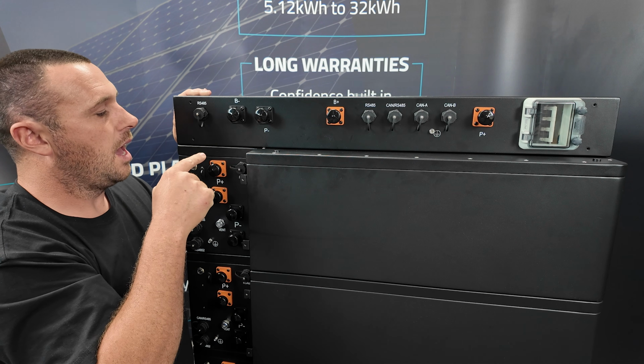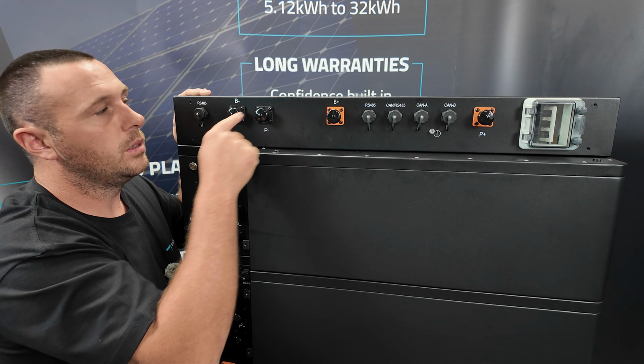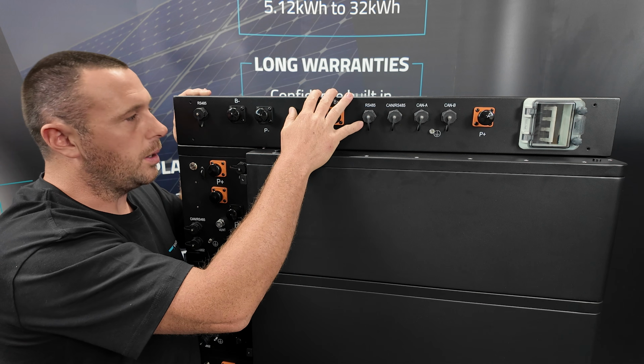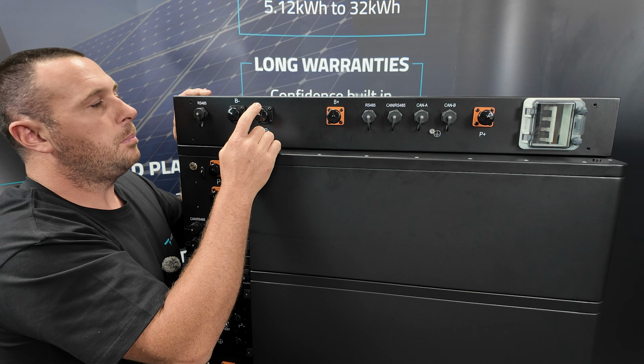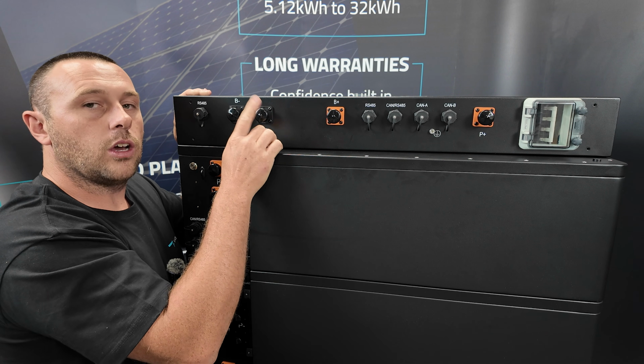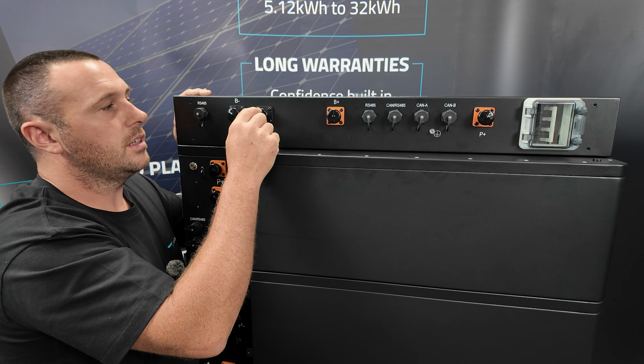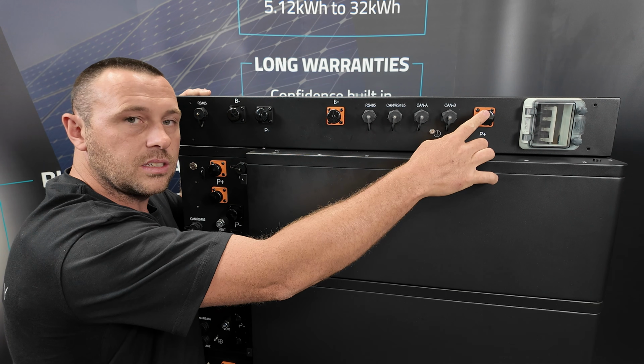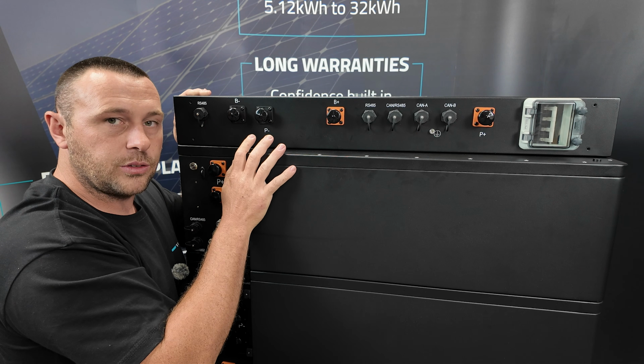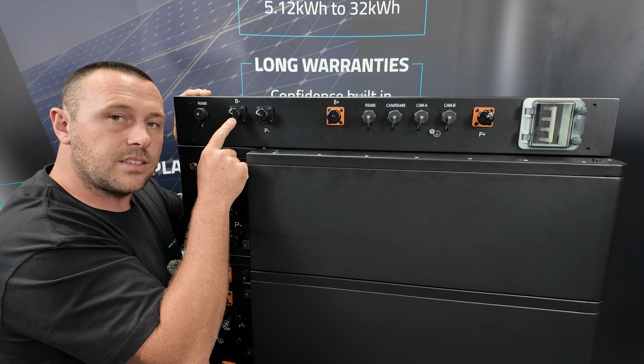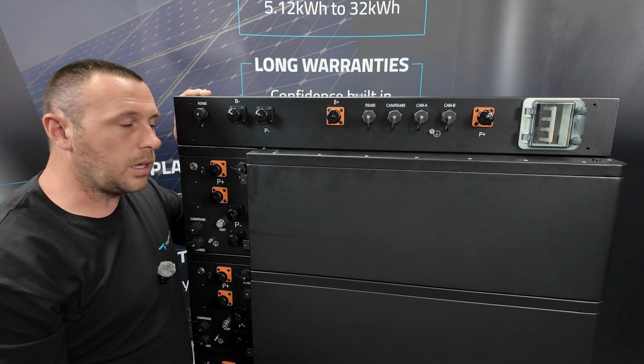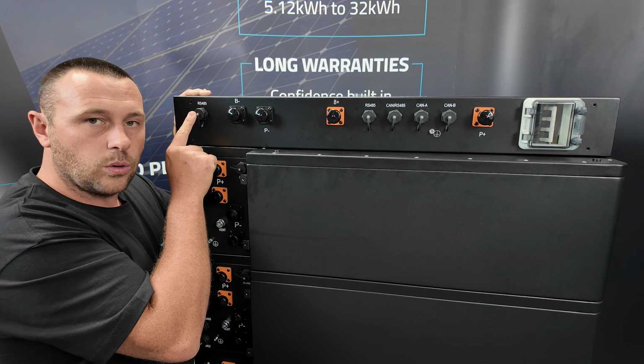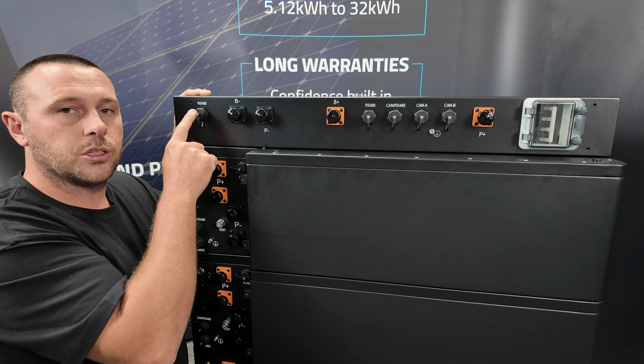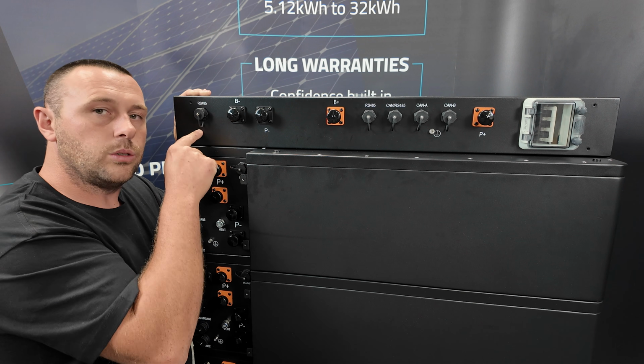So this is the output from the battery module below to here to the top control panel. This is the battery negative lead that goes out to your inverter again. So this is the negative and this is the positive that you will take out from the battery stack to your inverter. And this is the battery negative for the modules below. And then this RS485 port is the communication from the top module to the control panel.